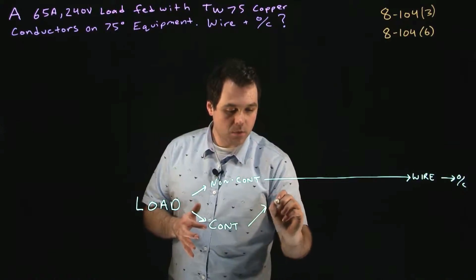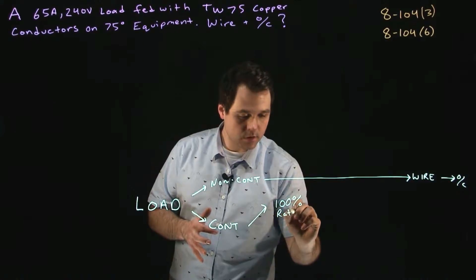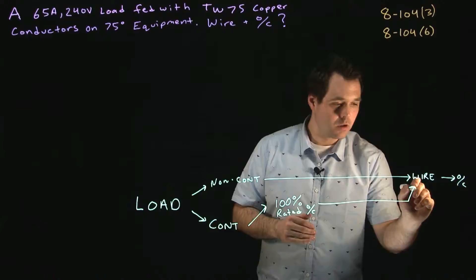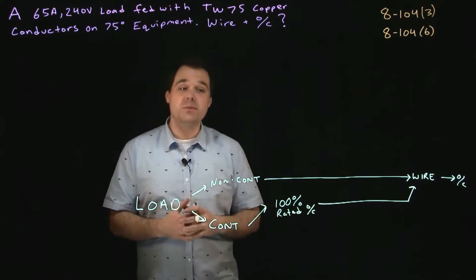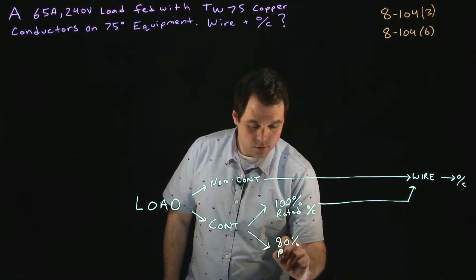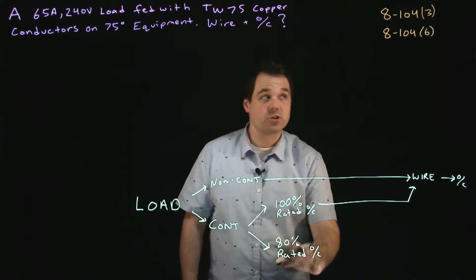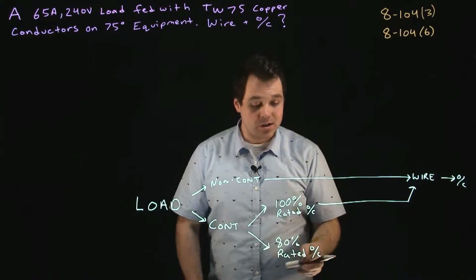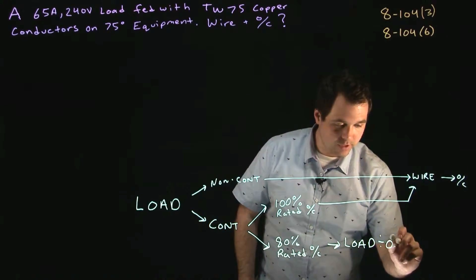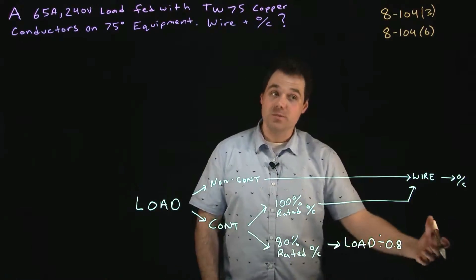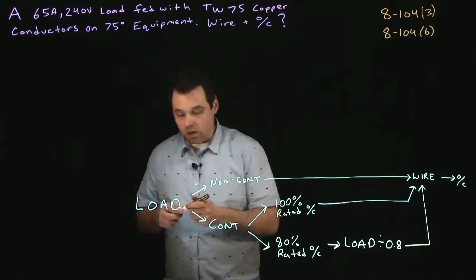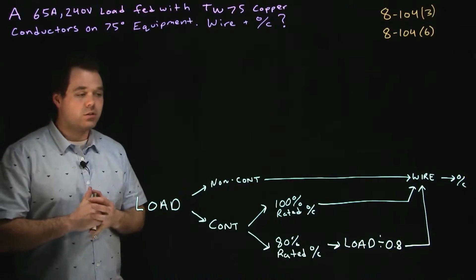If you have a 100% rated overcurrent device, the breaker can handle 100% continuous load all the time — no problem — so you just size your wire and you're good to go. However, the most common installation in the field is an 80% rated OC, which is addressed in 8104 Subrule 6. In that case, you take your load, divide by 0.8, and use that result as your minimum ampacity to size your wire — ensuring your load does not exceed 80% of the breaker rating.